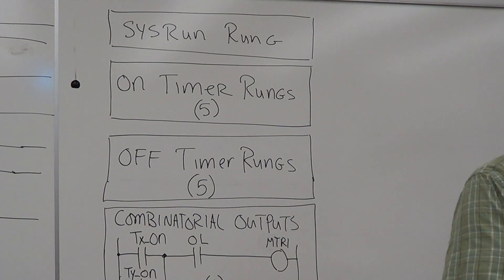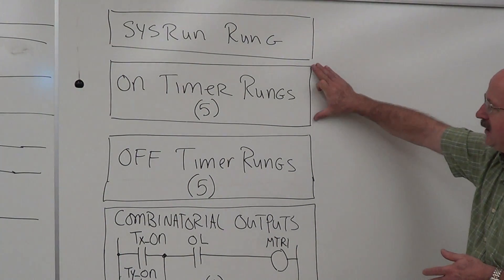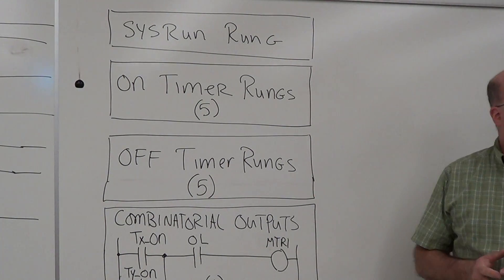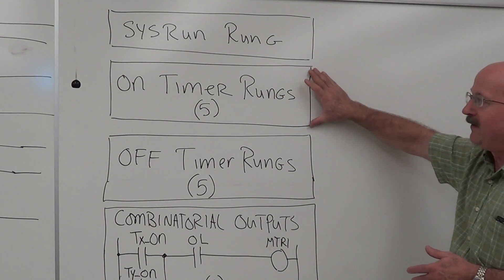We already know that we want another output control to take care of the overloads, because we can't put an overload after an off-delay. If we do have an overload condition, we want to shut everything down. So set this up in functional blocks. Start with your sys run.